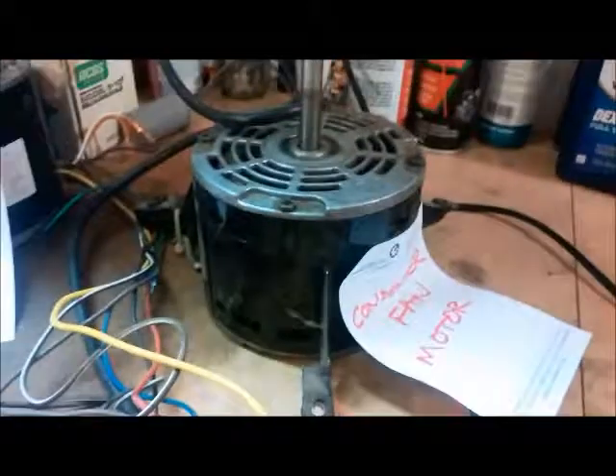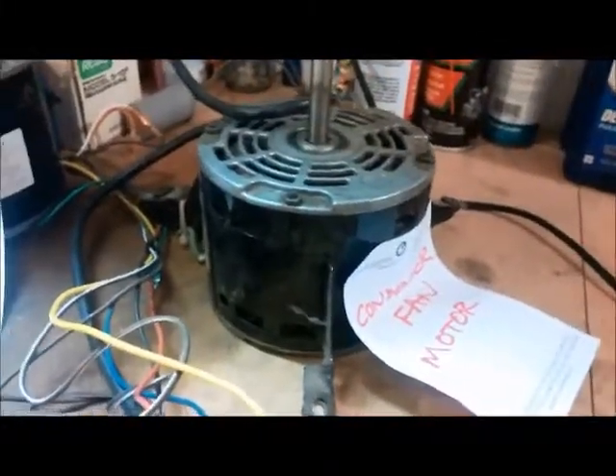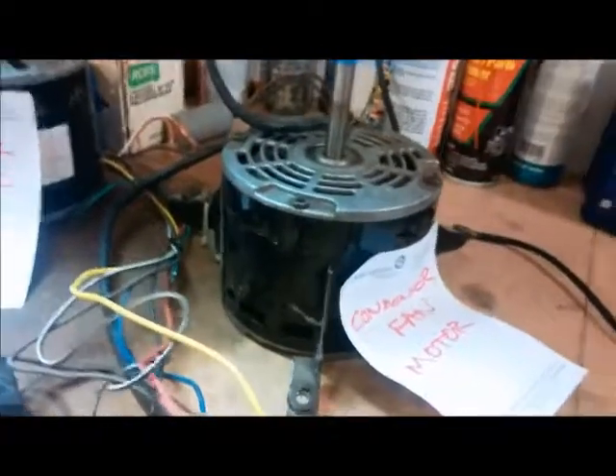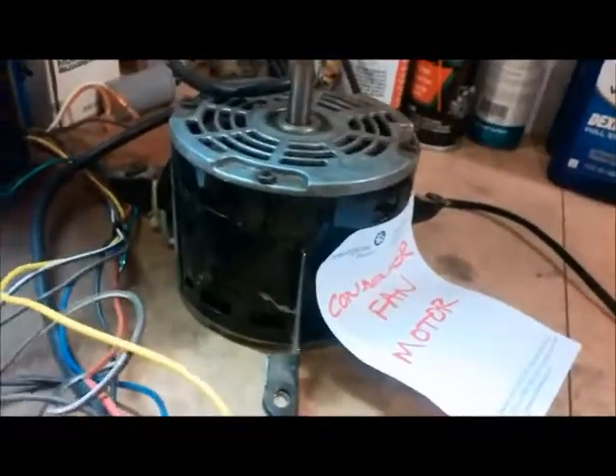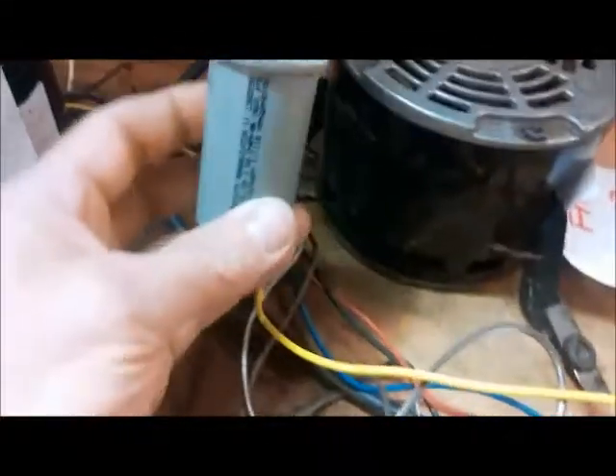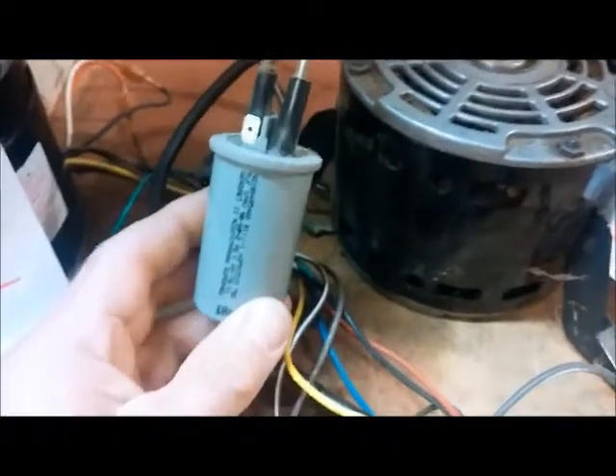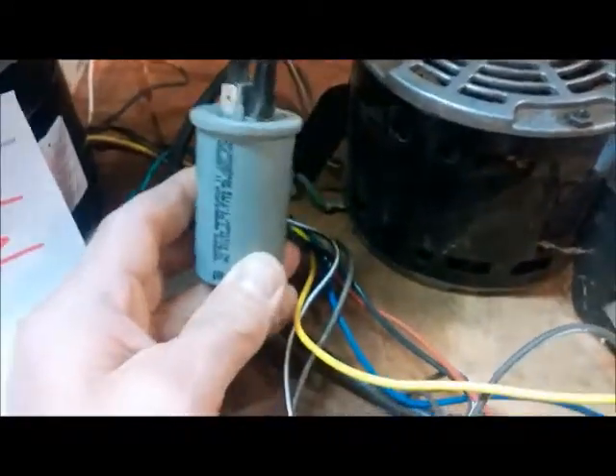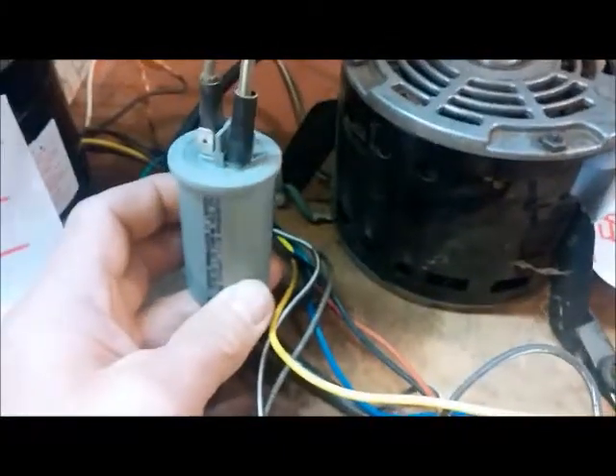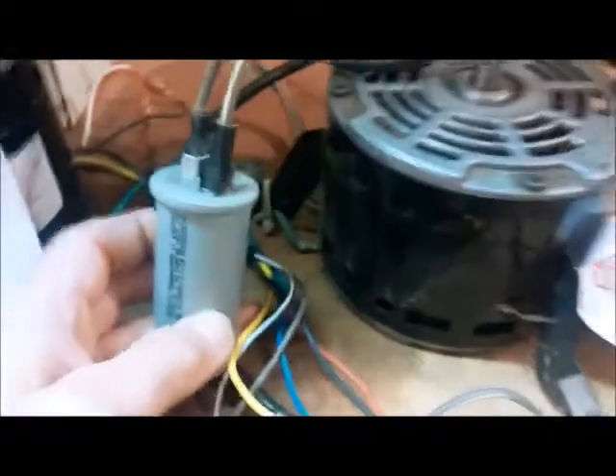Okay. Condenser fan motor, as well as our compressor, should be running. You should hear the two different motors. You'll hear that twang in the compressor outside underneath the fan motor. So if you don't hear the compressor running, you could have a bad capacitor. Today we've only got a 5 microfarad cap hooked up to the condenser fan motor. Typically you would have a dual capacitor out at the air conditioner, something like 25 by 5 or 30 by 5, 60 by 5 if you had a 5-ton air conditioner. So the bigger one is going to start your compressor, and the smaller one's going to start your fan motor.